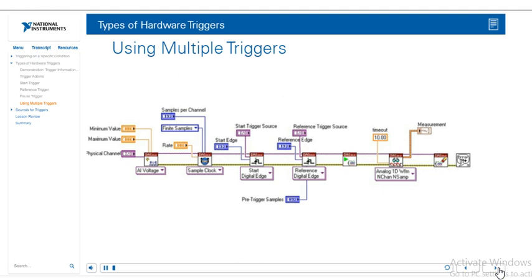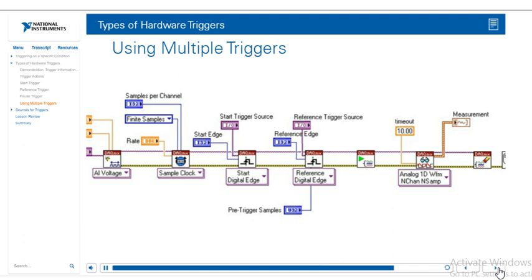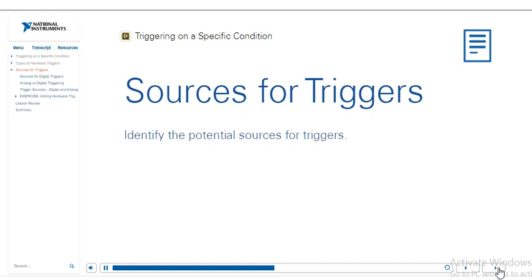It's also possible to use multiple triggers. In this case we're using a start digital edge trigger to start our acquisition, but we're also combining that with a reference trigger. So the start trigger will kind of start the whole system, then I'll be collecting data in my circular buffer until I get the reference trigger, and I'll have the pre-trigger samples and post-trigger samples.